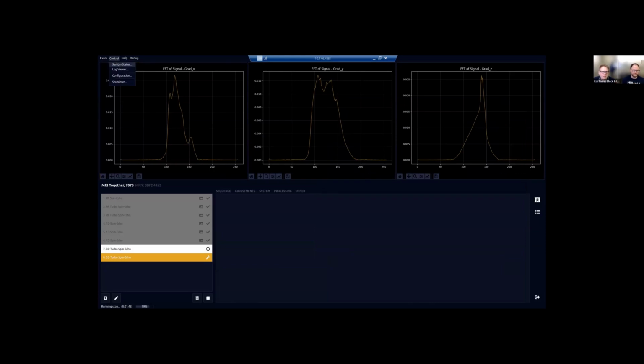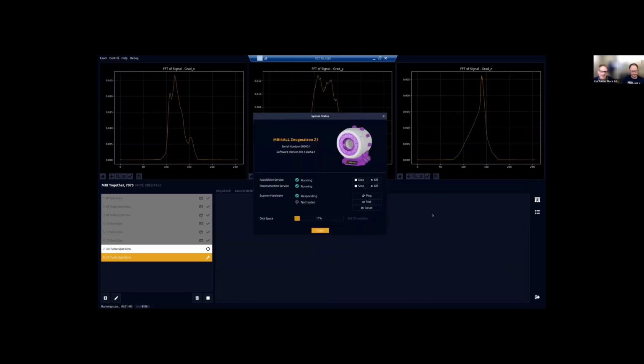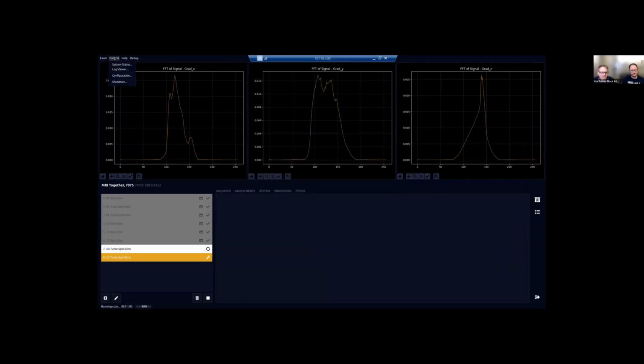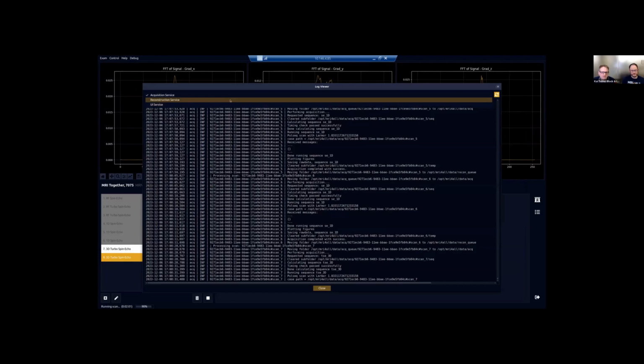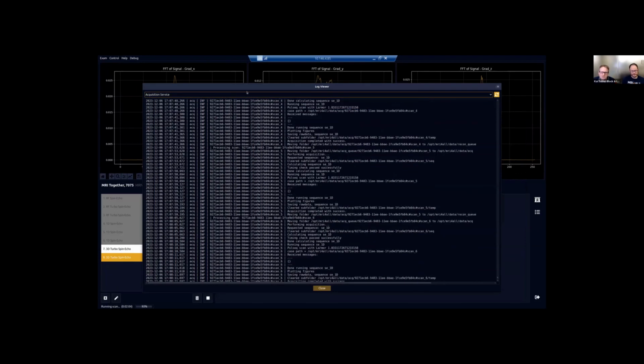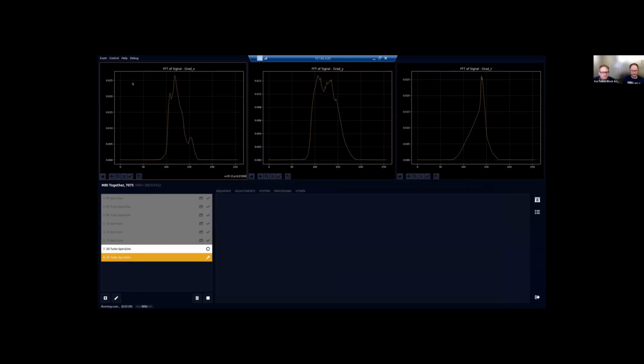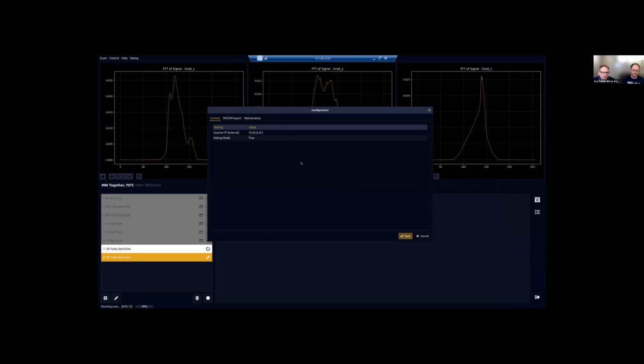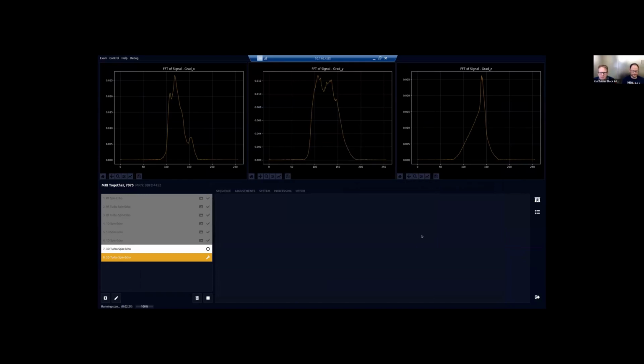What else do we have here? We have a system status button where you can check the status of the scanner. You could also start and stop the different services if something gets stuck for whatever reason, but luckily it's working pretty robustly. There's a log viewer where you can see the log outputs from the different services, so if there's a problem with the sequence, you would be able to see that here. And then what else do we have? There's a configuration dialog where you can set up certain things. You can configure DICOM nodes if you want to push DICOM images in the end to a PACS or something like that, so this exists as well. And then I think the scan should be done any second.